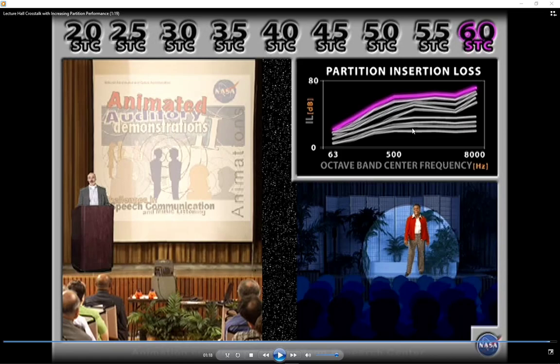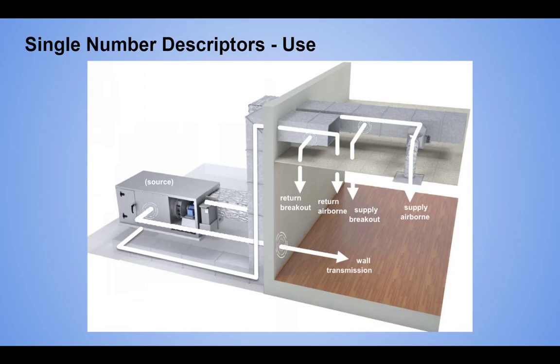As we move up STC, it's not a straight number — we're still getting a little low end. If we were doing recording, distance learning, or streaming, we'd pick up that low end and it would manifest as artifacts. Background noise in the space and wall transmission both contribute, but if we don't fix the mechanical equipment and get that level down, whatever we do with the wall is irrelevant — those sources will be much louder. Also, the idea that you just need to put absorption on the wall to fix it will only get you about 6 dB total.